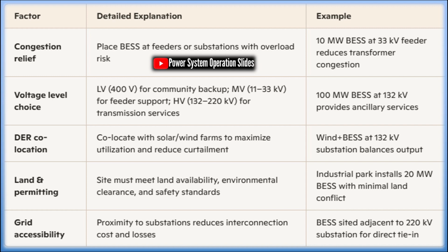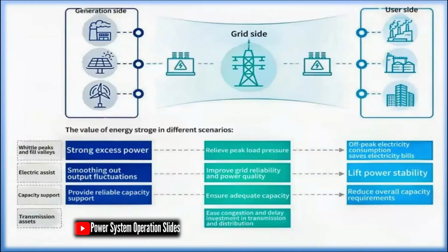This case study illustrates how properly sited distribution-level BESS can provide substantial value by deferring capital expenditures and enabling distributed energy resource integration. The third question addresses higher-order sizing requirements for transmission and distribution networks, recognizing that BESS sizing is a multidimensional problem that extends beyond simple power (MW) and energy (MWh) specifications. While primary sizing parameters such as power rating, energy capacity, C rate (the ratio of power capacity to energy capacity), round-trip efficiency, and state of charge (SOC) operating window provide the foundation for BESS specification, advanced constraints must also be considered to ensure reliable and economic operation.